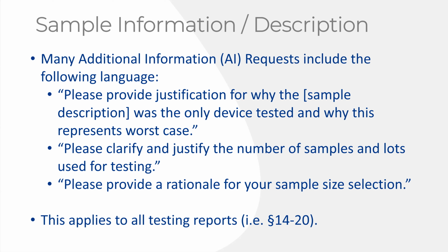Why? Because then that information will be very clear as the FDA wants it, and it will be consistent across all your testing reports. Here's the justification for why we chose this one, and here's the write-up of it, and here's a picture of it. Please insert this in the test report. You're helping the lab. If they have a problem with it, they'll discuss it with you.